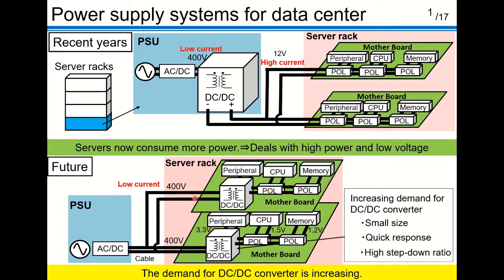Also, to improve efficiency, CPU and other equipment are handling lower voltage. Considering this background, the structure of server racks is expected to be such that power supply is distributed at high 400 DC voltage close to the motherboard, and stepped down significantly by an isolated DC-DC converter placed on the motherboard. At this time, such DC-DC converter must be small, have quick response, and be able to achieve high step-down ratios.